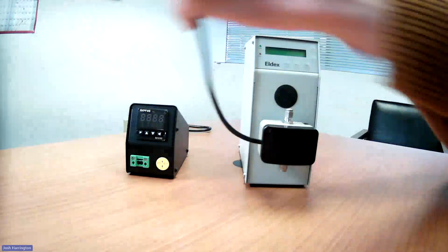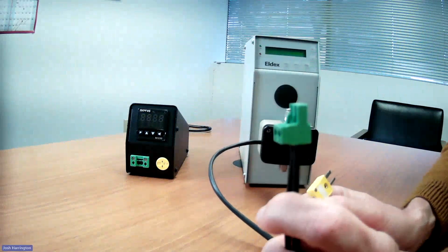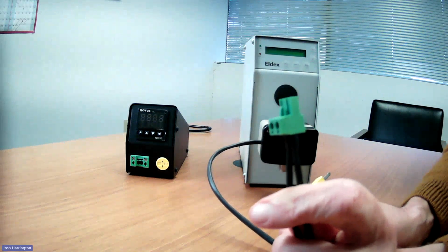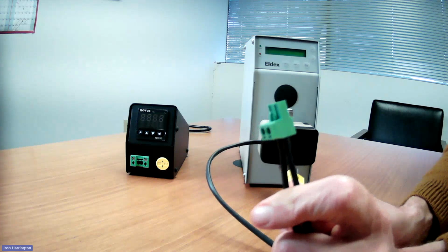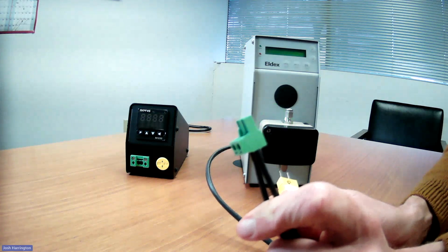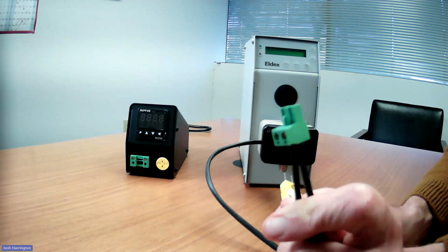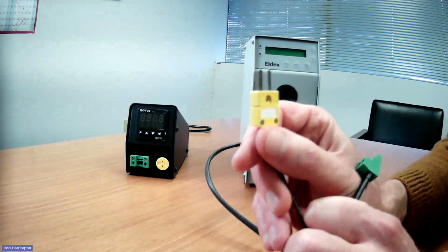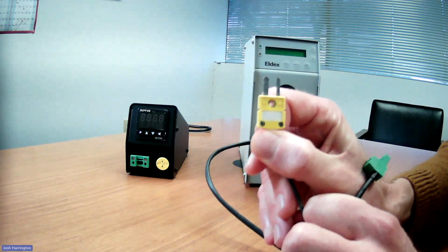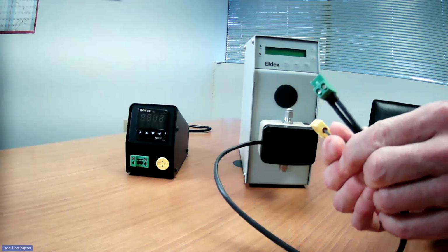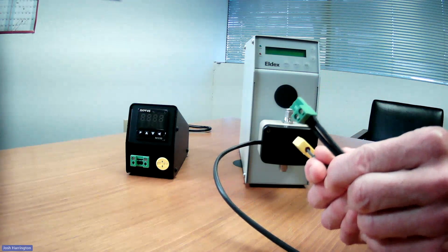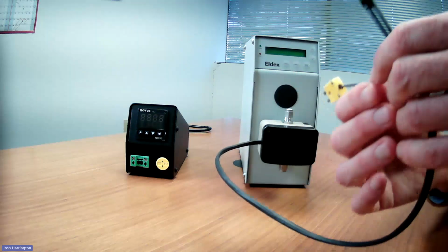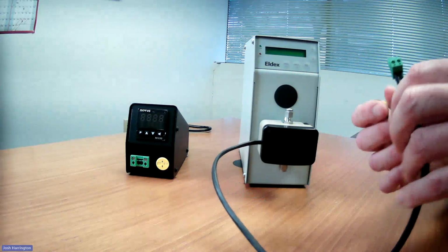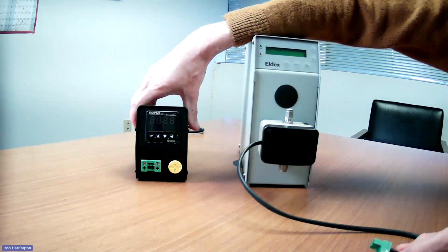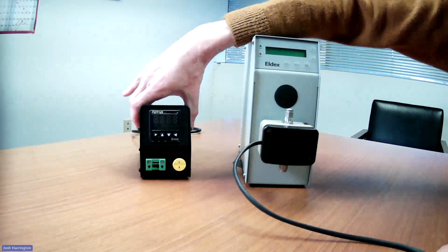Now, the connections, we've got the green connector, which is a standard Phoenix power connector, and we offer a mating connector if that's required, or these are widely available. And then you've got a K-style thermocouple. So this can be connected directly to your PLC, if so desired, and you can control the device directly that way. Or if you would like some sort of benchtop solution or are not running with a PLC, you can use our optional controller here. And now this is sold separately.